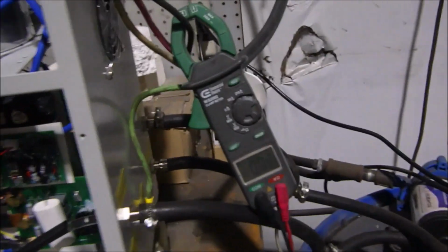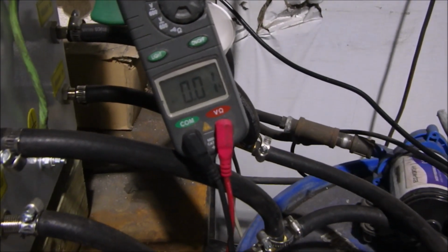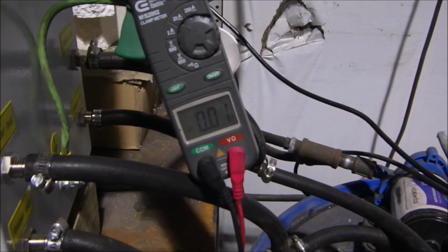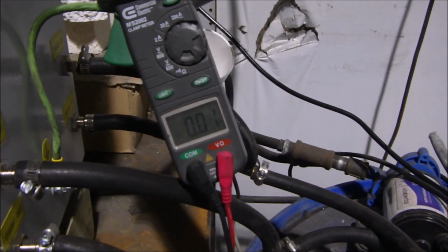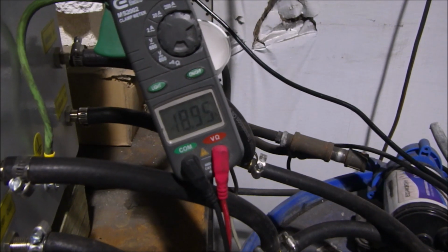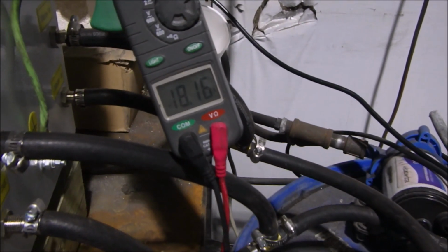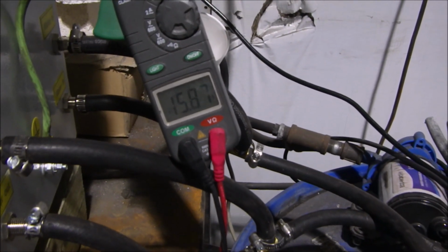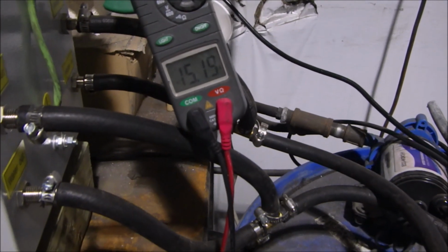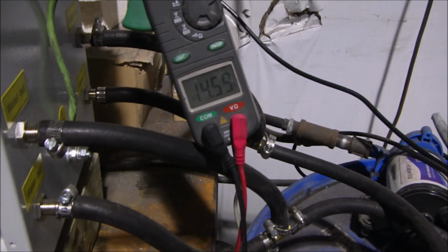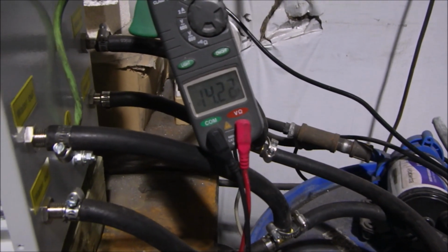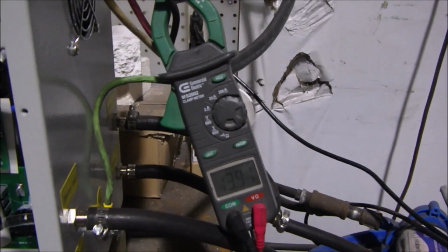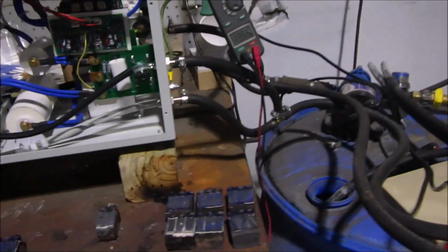We'd been cycling water through a barrel back there, but our pump died today. So we're going to kick this machine on and show you the amps on one of the legs. I checked all the legs earlier today and they're pretty much the same. Kick it on. You see that? 18, 19 amps. That's when it first turns on, and it settles down to about 15 after the capacitor charges up. So 15, maybe 19 if you really want to stretch it.